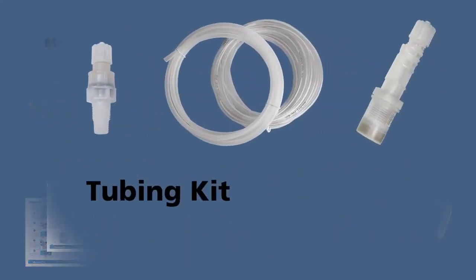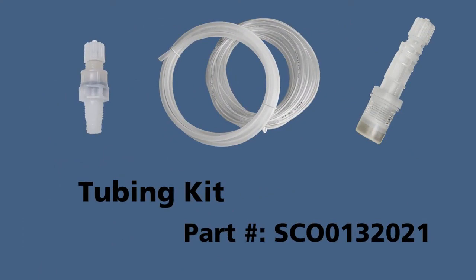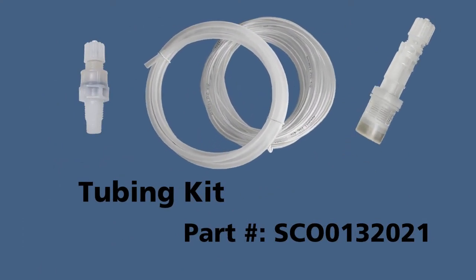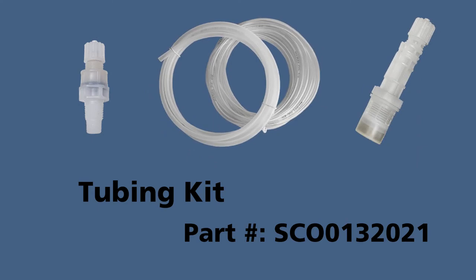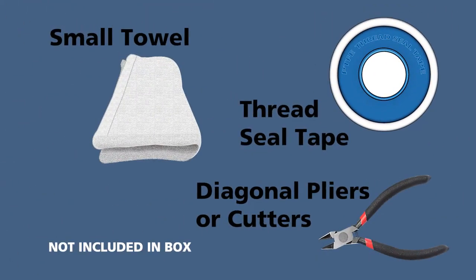The tubing kit includes injection valve for 3/8 or 1/2 connection, foot filter, 6.5 feet of rigid polyethylene discharge tubing, clear flexible PVC suction tubing, and PVC bleed-off tubing. You will also need thread seal tape, diagonal pliers or cutters, and a small towel, none of which are included in the eMP metering pump box.